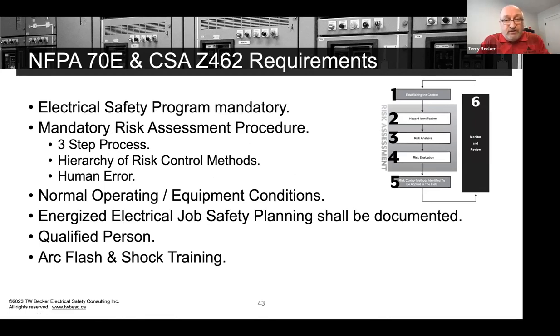So just paraphrasing the requirements, an electrical safety program is mandatory, and that electrical safety program should have a mandatory risk assessment procedure. And I recommend work task-based because 70E and Z462 are work task-based. We need to understand normal operating or normal equipment conditions, and the worker needs to document their arc flash and shock risk assessments. And I call it an energized electrical job safety planning form.